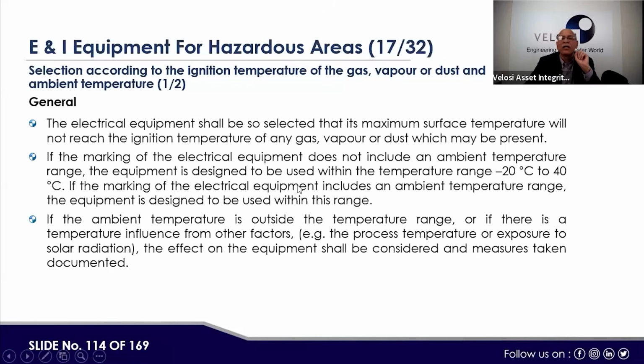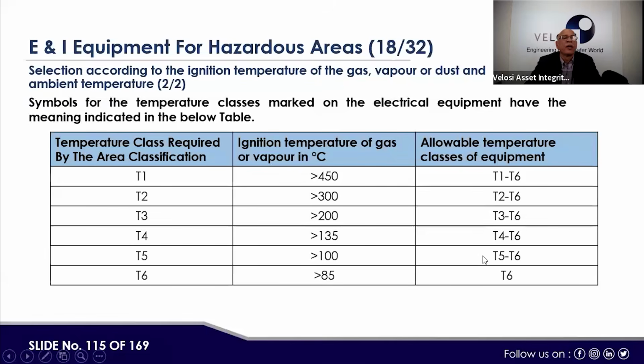If the marking of the electrical equipment includes an ambient temperature range, the equipment is designed to be used within this range only. If the ambient temperature is outside the temperature range, or if there is a temperature influence from other factors, for example, process temperature or exposure to solar radiation, the effect on the equipment shall be considered and measures taken and documented. Here, the symbols for the temperature class marked on the electrical equipment have the meaning indicated in the below table. For example, T1, T2, T3, T4, T5, T6, we studied earlier also.